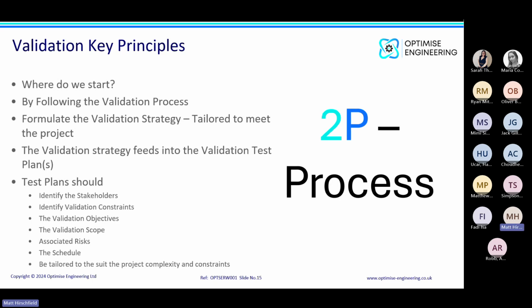Validation scope. So test boundaries, test specification that should be aligned with our requirements. Test expectations, expected results. Part of that test effort or that test case should be to describe what the intended outcome is. It shouldn't just be a case of does it work. It should be a case of what happens when we do this. This is what should happen when we follow these steps. Is that correct or not? And that feeds back into our acceptance as well. So there may be more than one step in a test case, depending on whether an individual step fails.